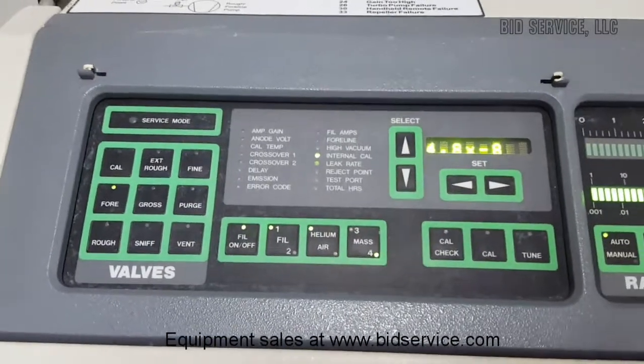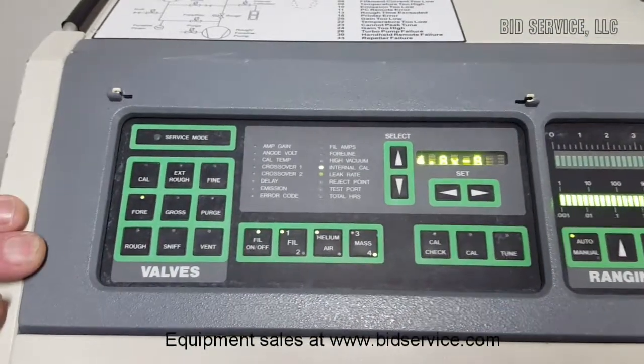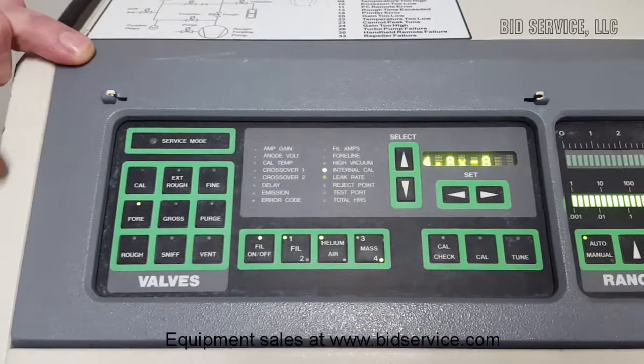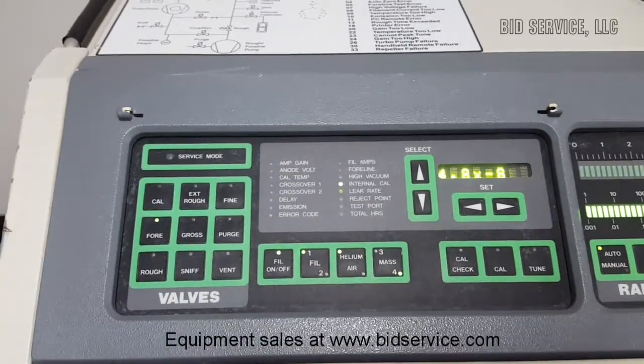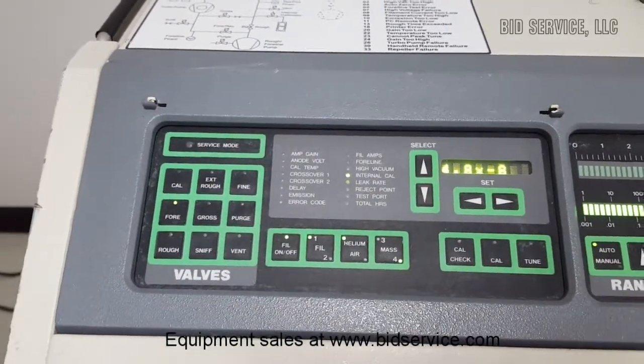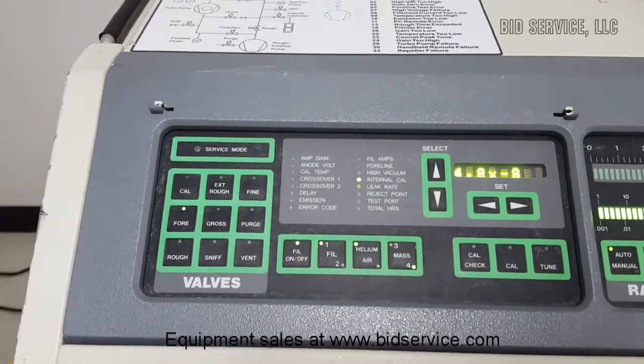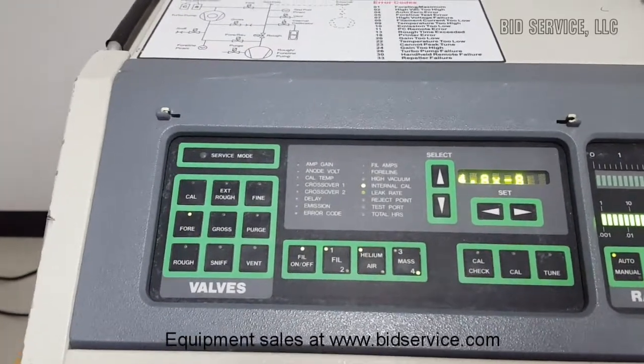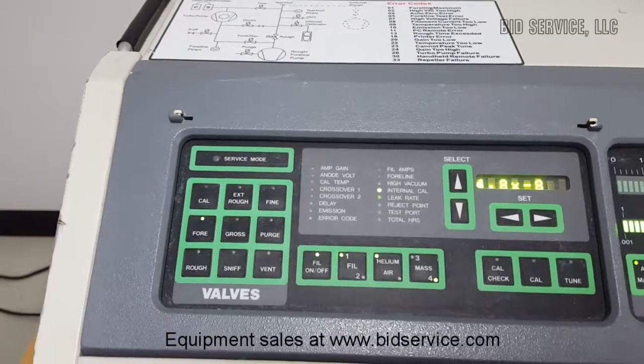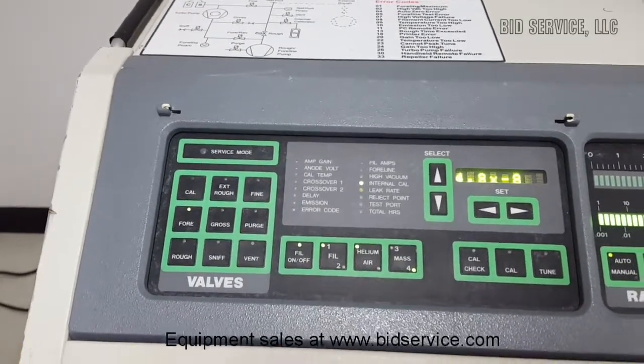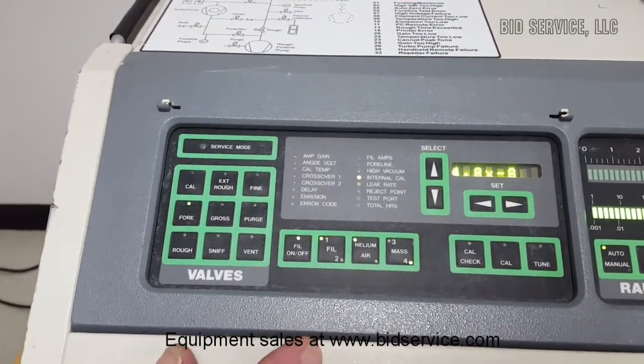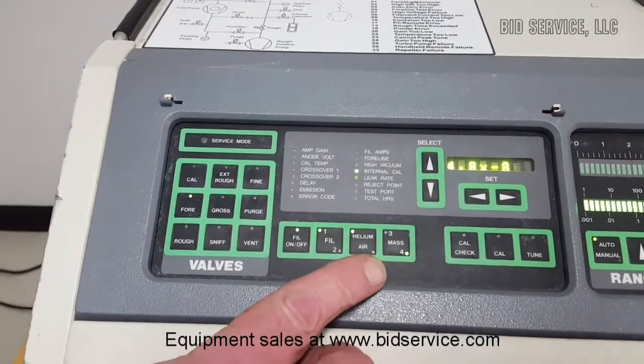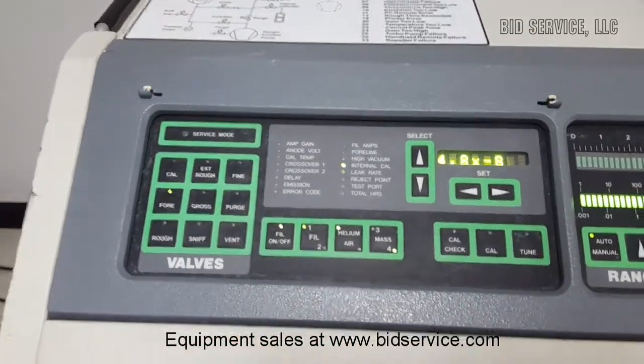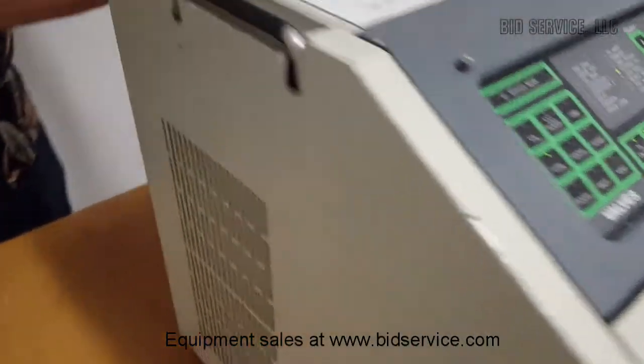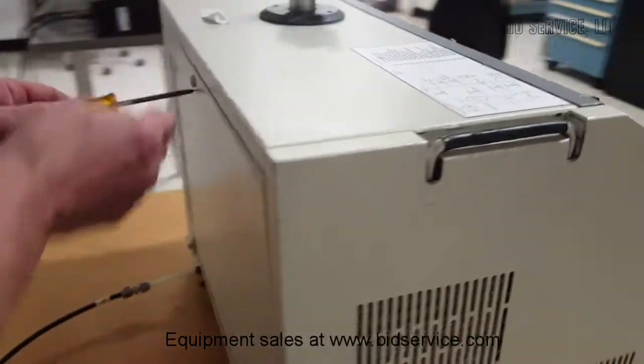Great caution should be used when using the service mode, because when you're in the service mode, you can manually sequence and operate the system. You have to be very careful with that, because the vacuum system in here has to be sequenced in the proper order. However, if you did want to switch between helium and air, what you could do is you come around to the back. You must be very careful because there is voltage present.